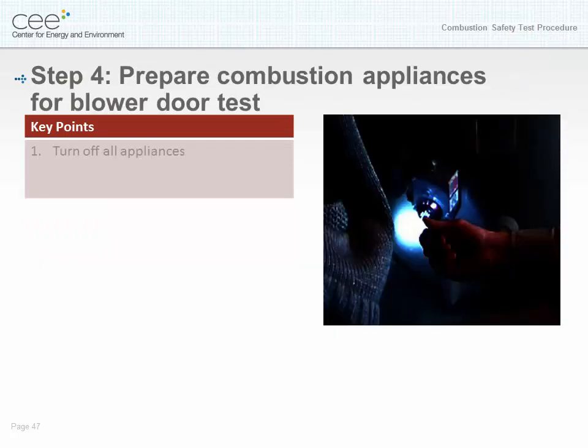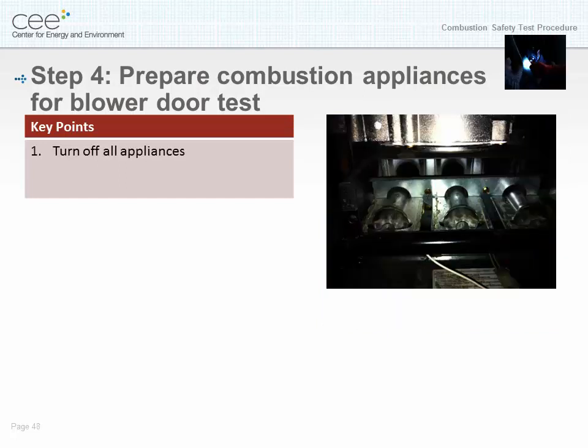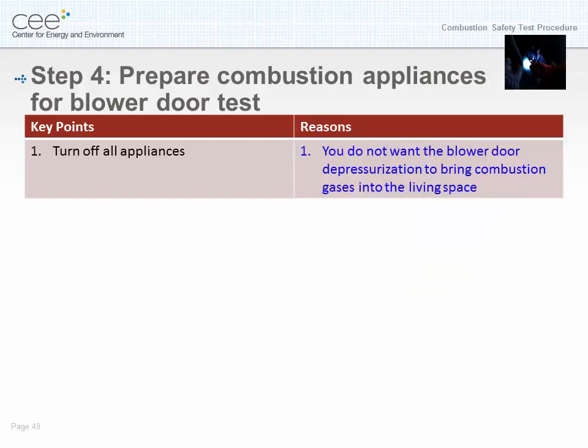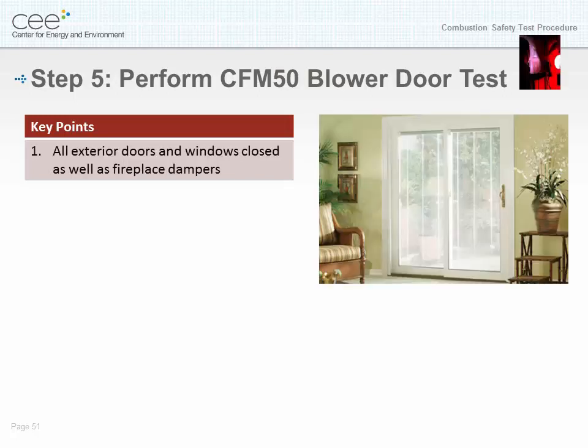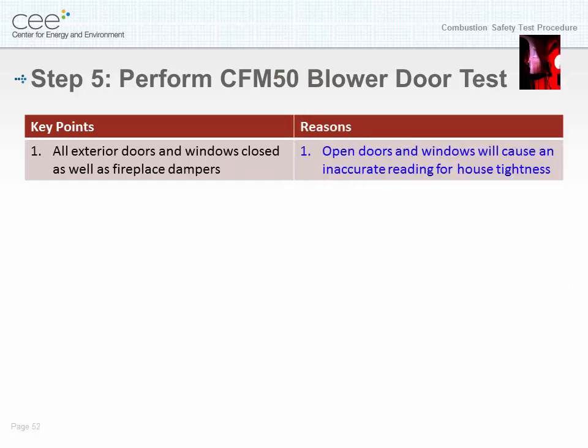Step four: prepare combustion appliances for blower door test. Key point: turn off all appliances. Reasoning: you do not want the blower door depressurization to bring combustion gases into the living space. Step five: perform the CFM 50 blower door test. Key points: all exterior doors and windows are closed as well as fireplace dampers. Reasoning: open doors and windows will cause an inaccurate reading for house tightness.